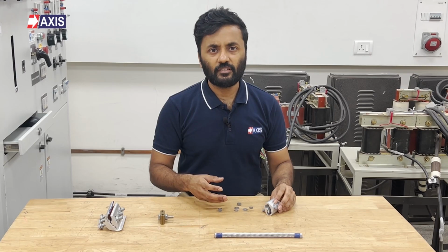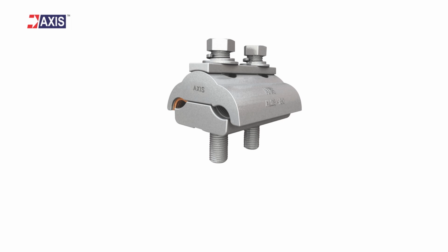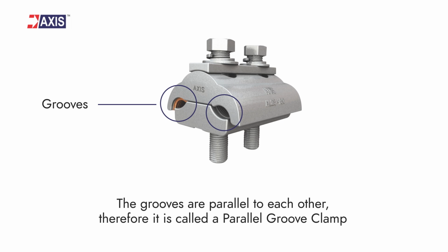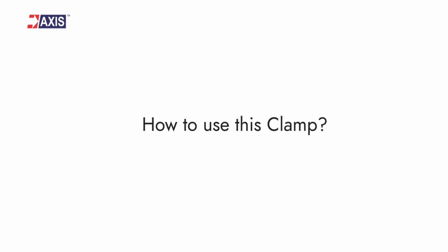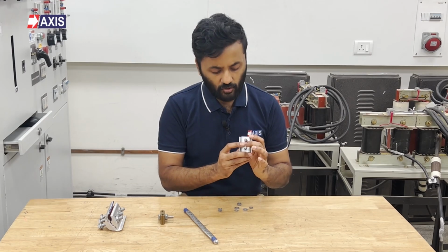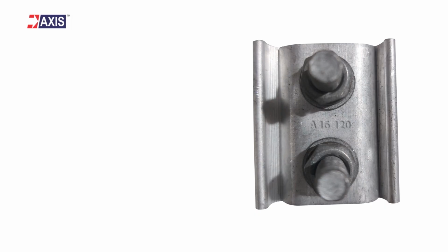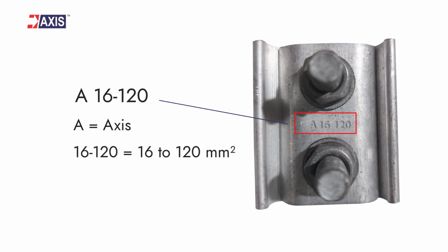A PG clamp is made by joining two parts. These spaces here are called the grooves, and the grooves are parallel to each other, which is why it's simply called a parallel groove clamp. Now, let me show you how to use this clamp. In this case, you can see a code over here showing A16120, where A stands for Axis and 16 to 120 means a conductor within a range of 16 to 120 mm square can fit inside these grooves.